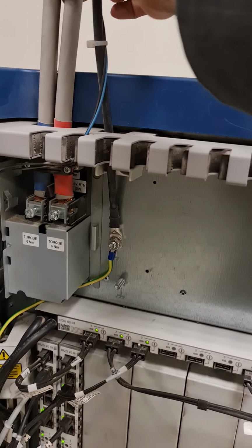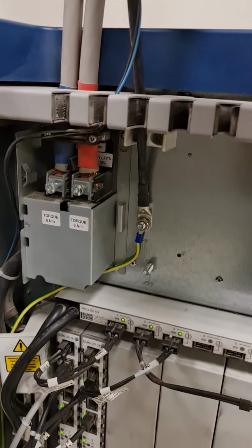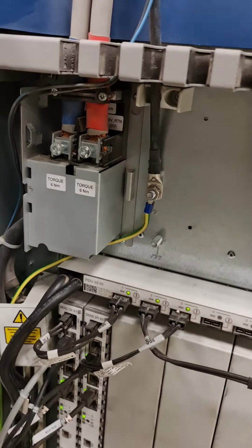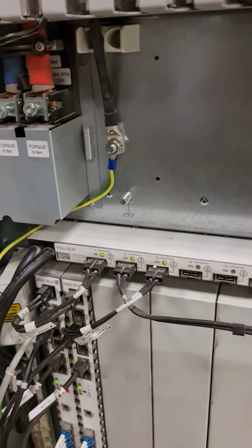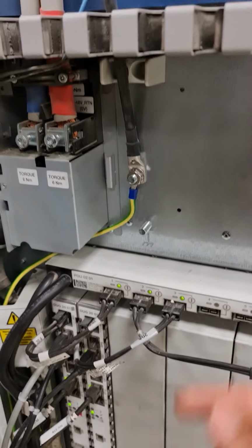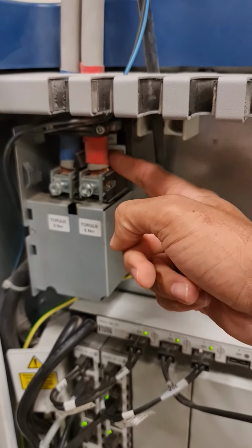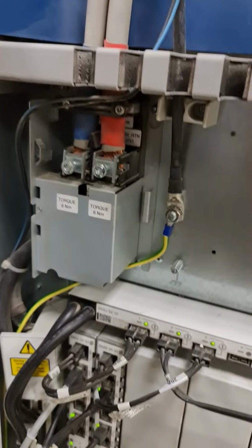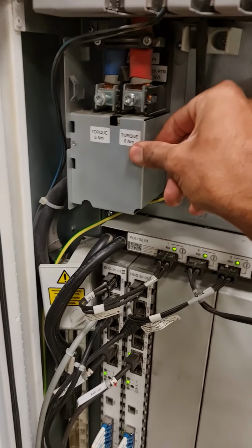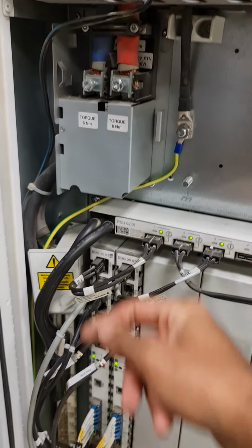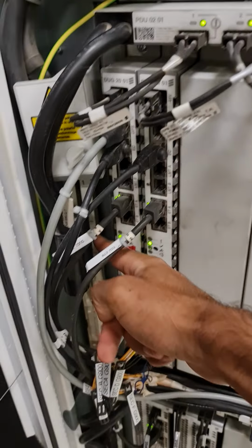This is a 54 volt, 48 volt requirement. 54 volt is optimal voltage and 48 volt is the minimum required for good working of the RBS. 0 volt is this side and minus 48 volt is this side, and these DC cables are feeding power to this bus bar on the end.